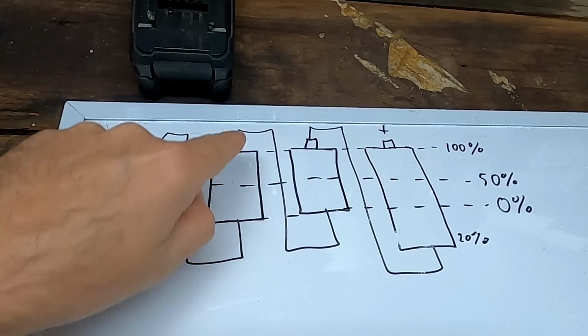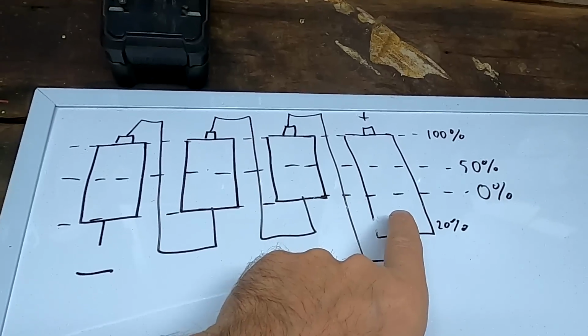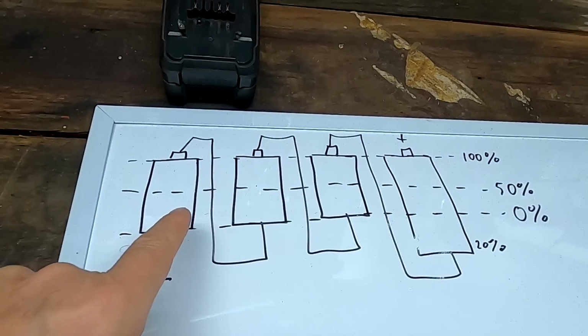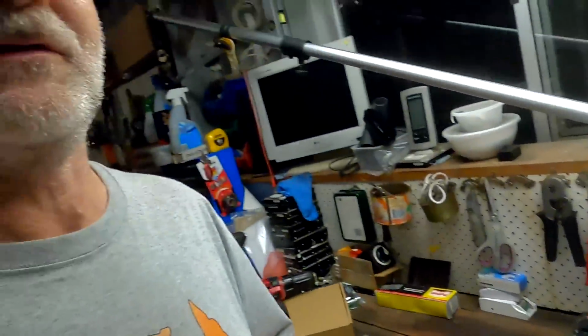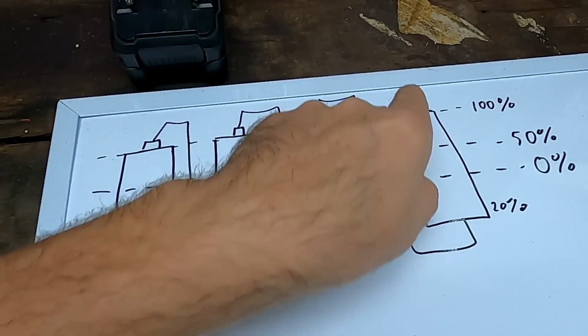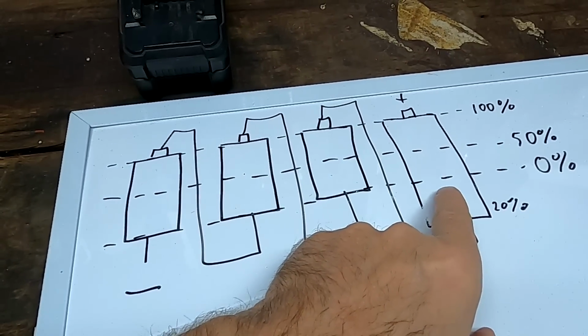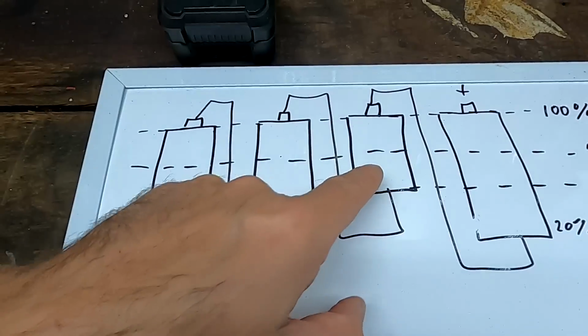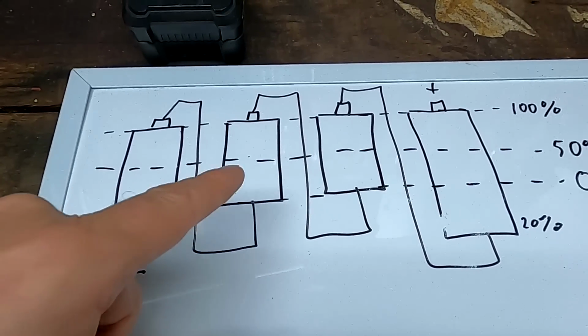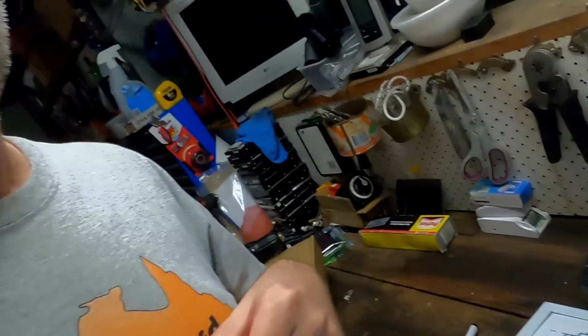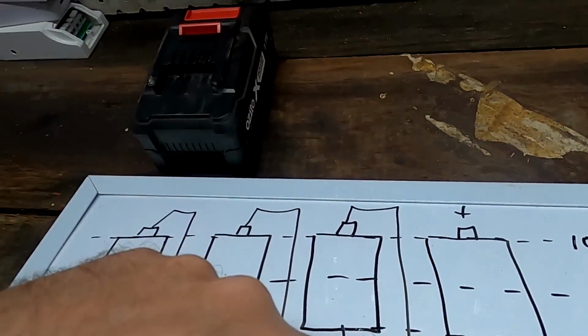So while there is 100 amps going through this series connection, you need a balancer taking away this energy and putting it into these cells at the same time, at a faster pace than we discharge these cells. And quite frankly, this is impossible. We will not find a balancer or even a stack of balancers which can deliver 100 amps of balancing current. Furthermore, you're not only discharging this one with 100 amps through your normal load, you would also need to take away 3 times 100 amps and put this balance current into each of these cells to prevent them from shutting down the BMS. So 100 amp load plus 3 times 100 amps for the balancer would make 400 amps for this one cell. Quite frankly, not possible and unhealthy for the battery.